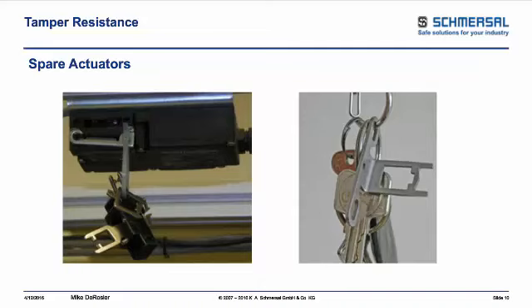The picture on the right, you can see there's one type of interlock key. The picture on the left, you can see a key inserted into a switch being purposely bypassed. But if you look at the wire tie, there's 3 or 4 different other keys on there for different manufacturers of interlock switches, so they can walk around and do that across all the machines on their floor.